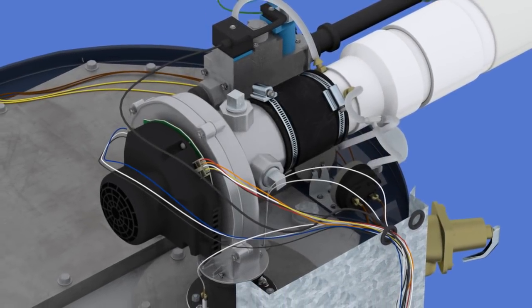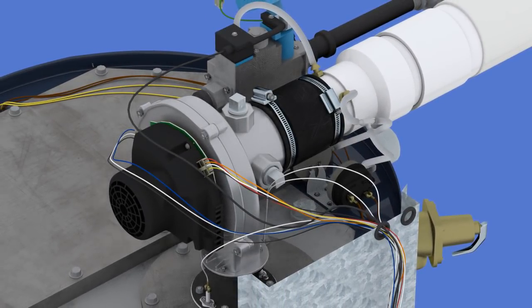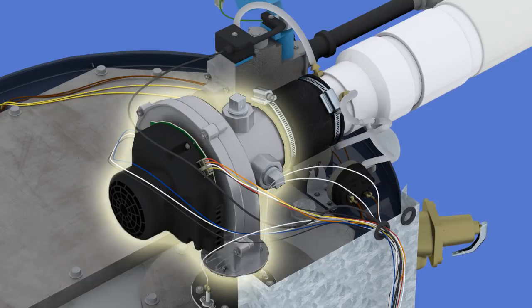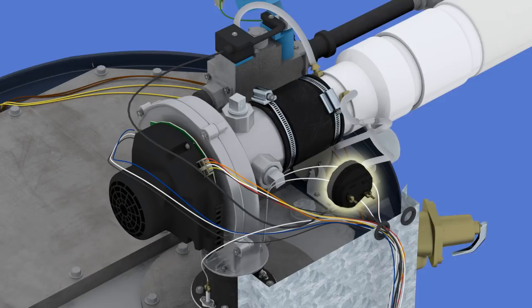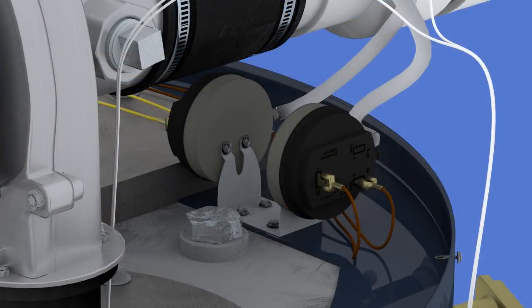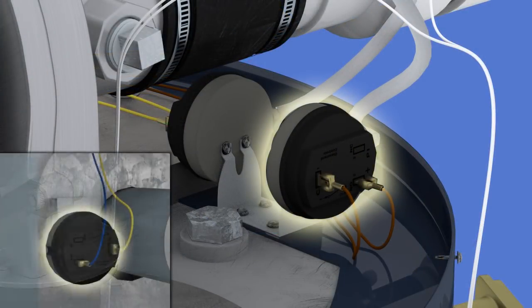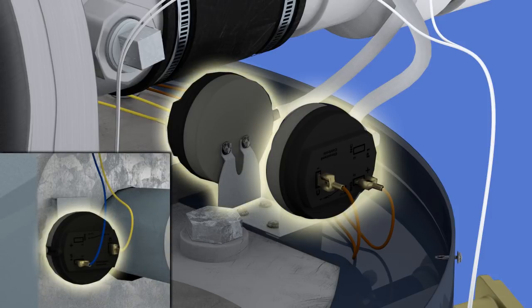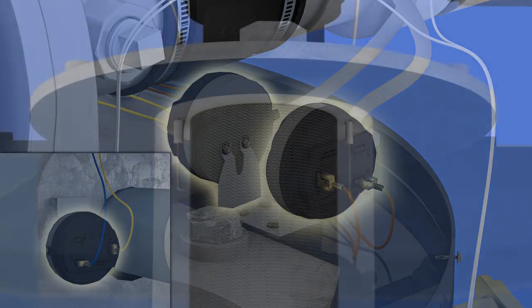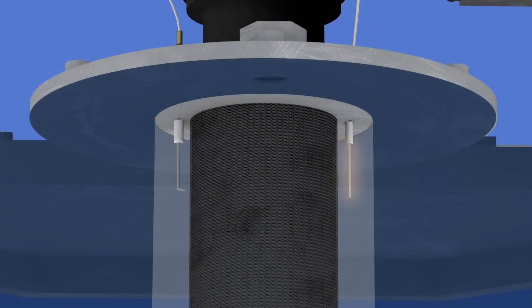When there is a call for hot water, the following occurs. The blower is energized to pre-purge speed and waits for the normally open air proving switch to close. This switch must close within 60 seconds. When the air proving switch closes and the normally closed blocked vent and blocked intake air switches are closed, the blower begins pre-purge. 5 seconds into pre-purge, the hot surface igniter is energized and warms up for 20 seconds.